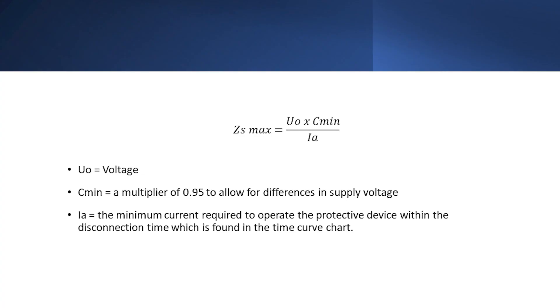Looking in appendix 3 of BS7671, we can see the calculation which shows how the maximum ZS values are calculated. We multiply the voltage by the C min factor of 0.95 and divide by Ia, which is the minimum current required to operate the protective device within the disconnection time.